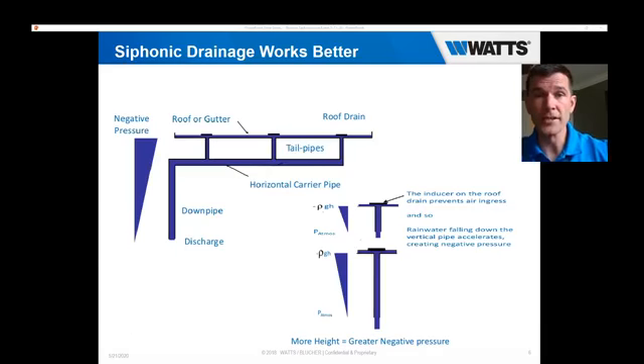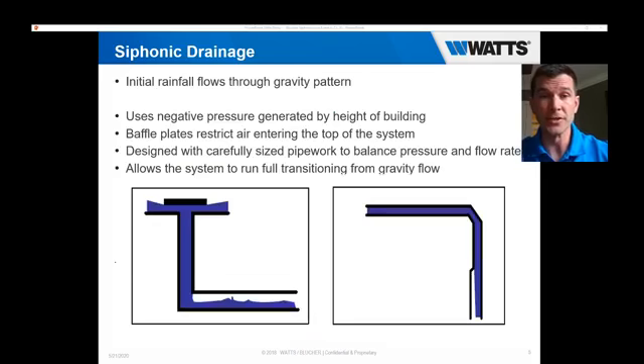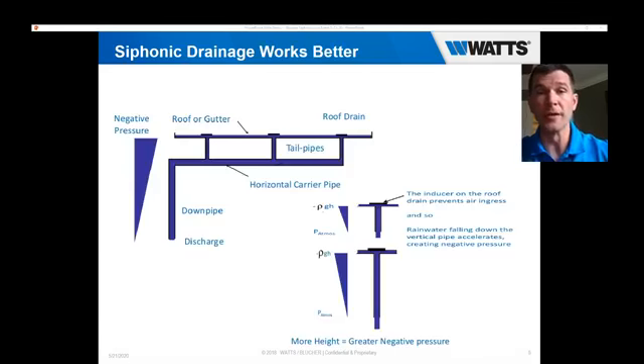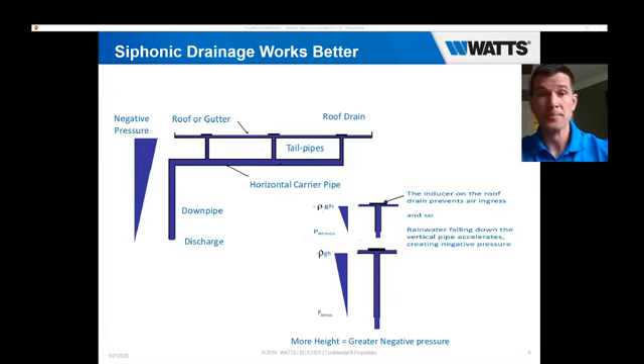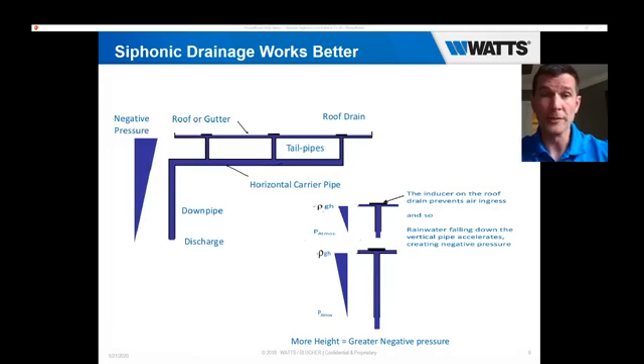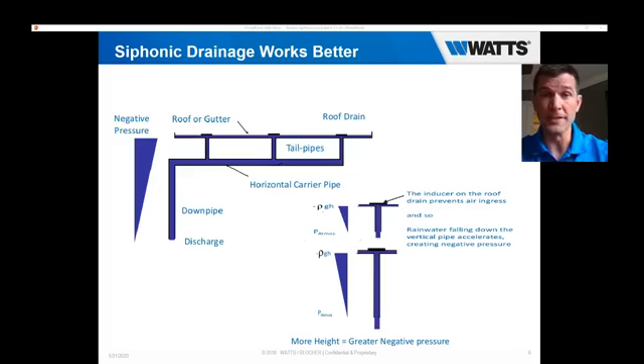With siphonic drainage, negative pressure is generated by the height of the building — the higher the building, the larger the pressure. As the water level gets above that siphonic plate, it draws in the water, completely fills the piping system, and allows the pipes to actually run completely horizontal as a carrier pipe through to the downpipe and discharge.